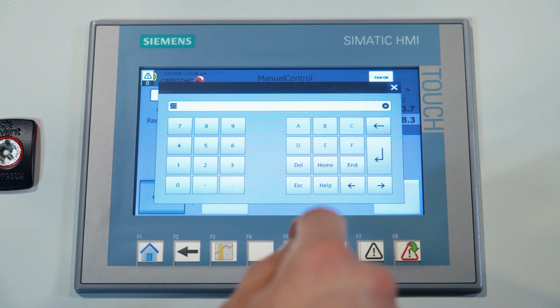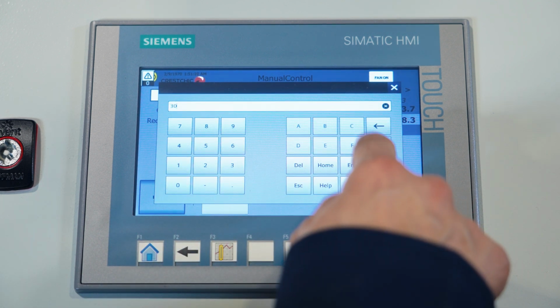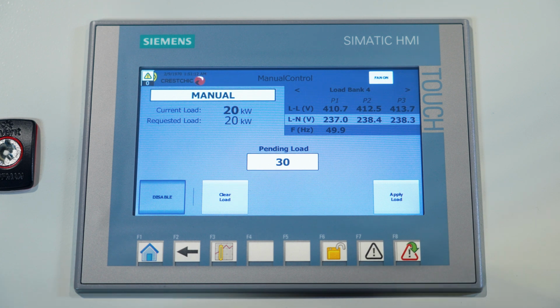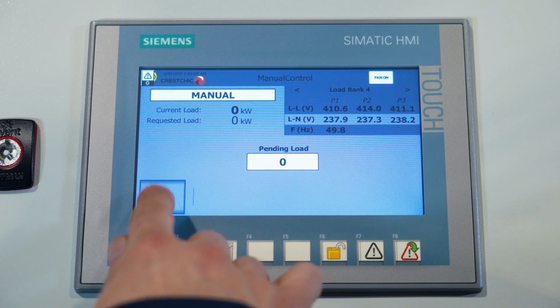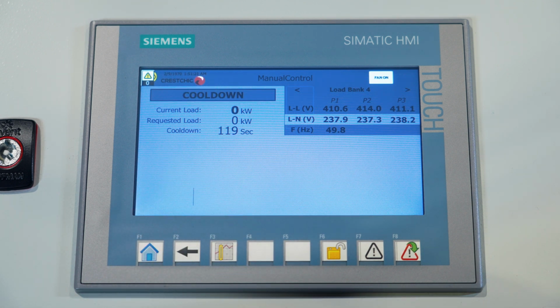Loads can easily be increased and decreased by inputting the new value and applying the load. Once the load test has been completed, the load is cleared and the controller will keep the load banks running for 4 minutes with no load to allow the load bank components to get down to a safe temperature.